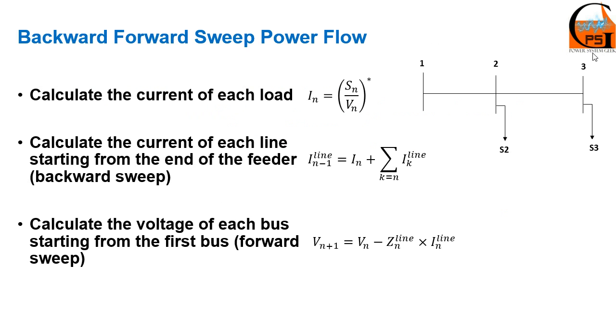Let's get started. Imagine that this is my distribution system — it is basically a part of a feeder with three buses, two loads, and my first bus is the slack bus. To do the backward-forward sweep power flow, we need to first calculate the current of each load. We do so by calculating the conjugate of S divided by the voltage of that bus. After that we need to calculate the current of each line.